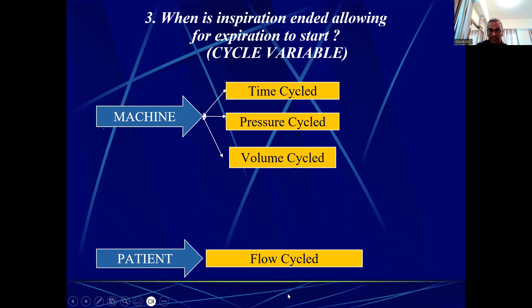Flow cycling is technology driven, too much technology needed, so not all ventilators have flow cycling. When somebody tries to sell you a ventilator, you have to make sure that flow cycling is available. Otherwise, it will only be time cycle. A lot of ventilators do not have flow cycling, so you have to make sure it is there. This is how it works. The x-axis is time and this is flow. It doesn't matter whether it is volume ventilation or pressure ventilation.